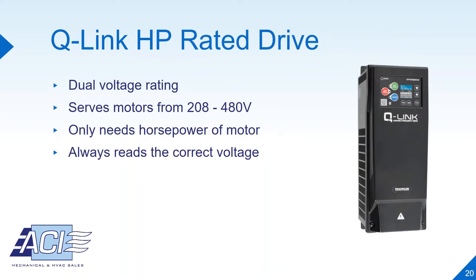The number one reason for VFD returns was that the voltage type was ordered incorrectly. Franklin Control Systems responded to this by developing the Q-Link horsepower rated drive, which has dual voltage rating, ensuring that it will always read the correct voltage. This model is good when the customer does not know the voltage needed since it serves motors from 208 to 480 volts, and the only information you need is the horsepower of the motor. For example, the same VFD will work at 5 horsepower, 480 volts, and 5 horsepower, 208 volts. Thus, it eliminates the possibility of incorrect voltage.